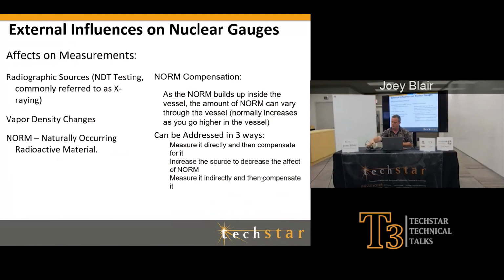We have one question from Roger. His question is: is it safe to assume the readings will be erroneous and inaccurate until you're up to process conditions? A lot of times the plant expresses concern when the levels are reading differently in a redundant application. Yes, yes. So we talked earlier about getting your - making sure you're at process conditions.